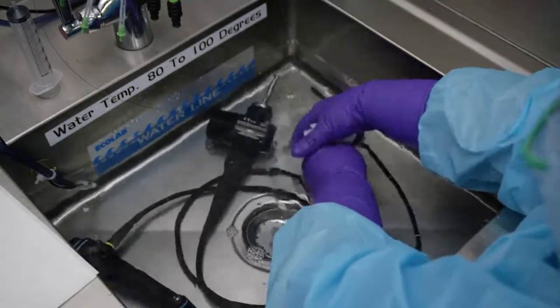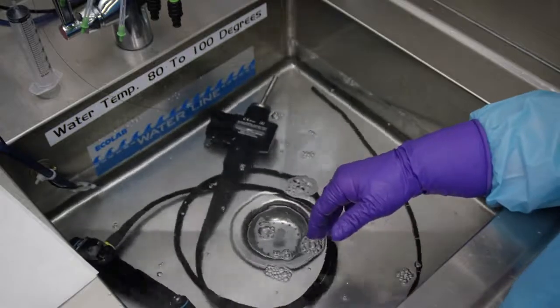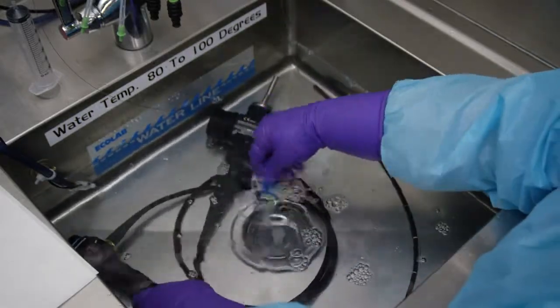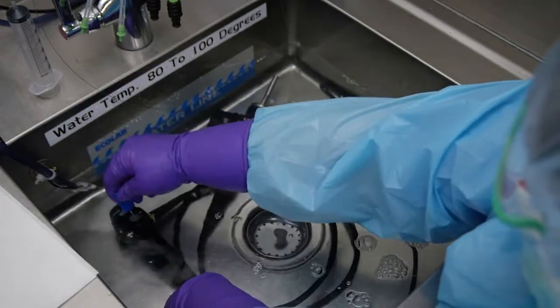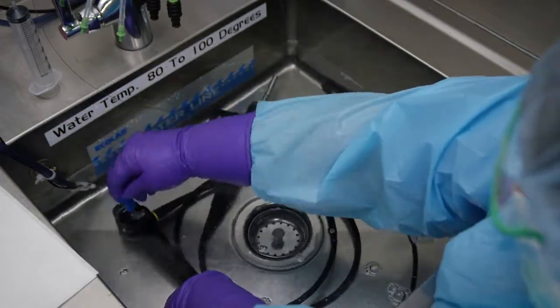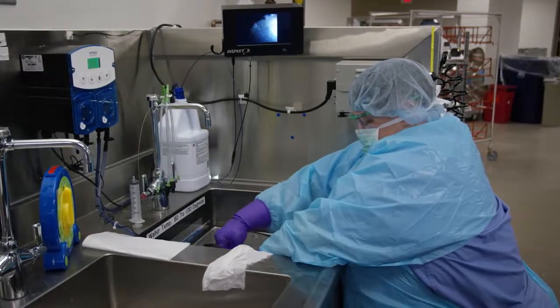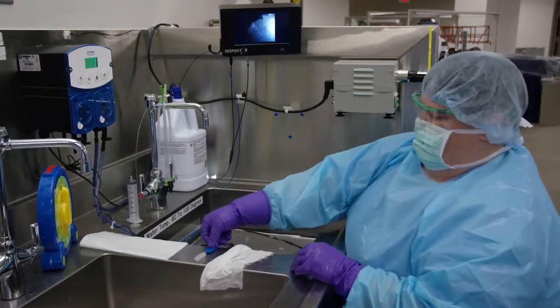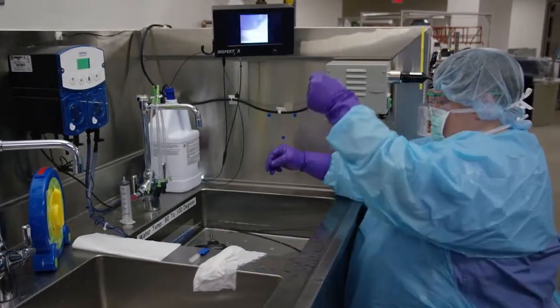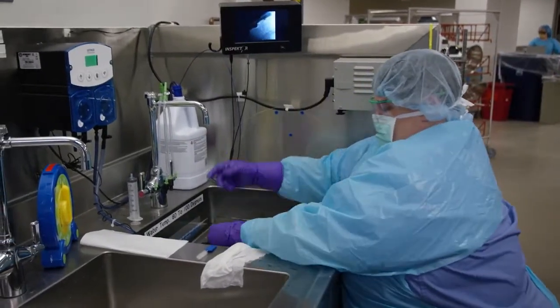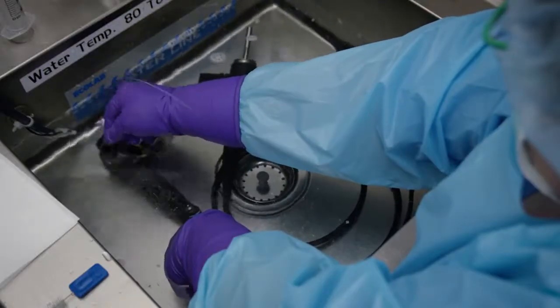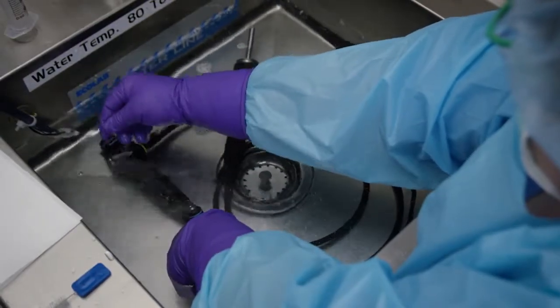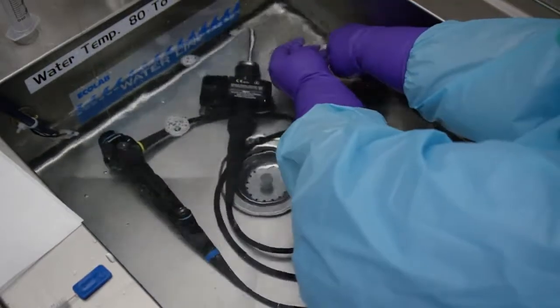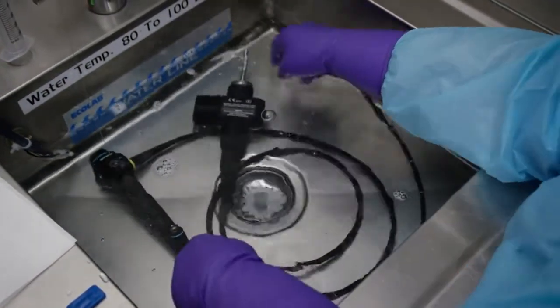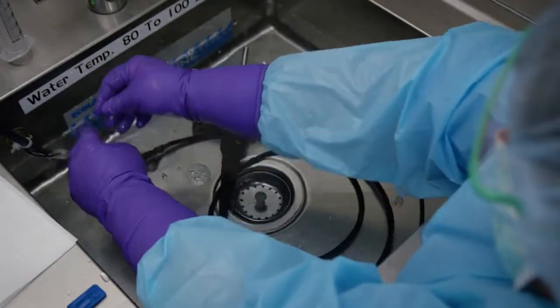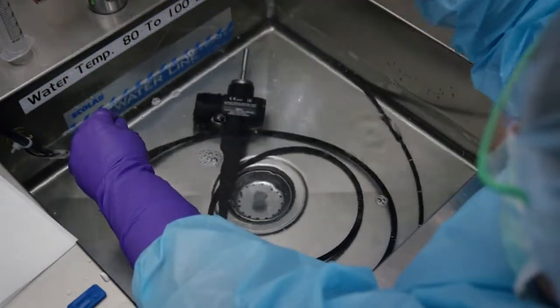To clean the interior, first choose the appropriate brush for the specific device or opening. Brush valve cylinders, openings, forceps elevator housings, and channels. Brush multiple times using varied brush strokes to help ensure that the brush friction reaches all areas within the lumen. This is important because brushing times have varied widely, and some parts are missed altogether or not done for the proper length of time. Rinse the brush between times as you pass through channels to remove debris. If you meet resistance, stop immediately and soften by soaking.